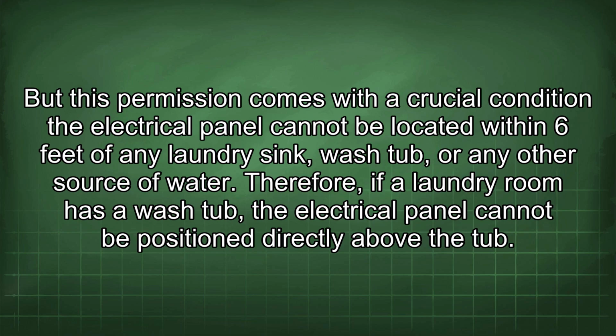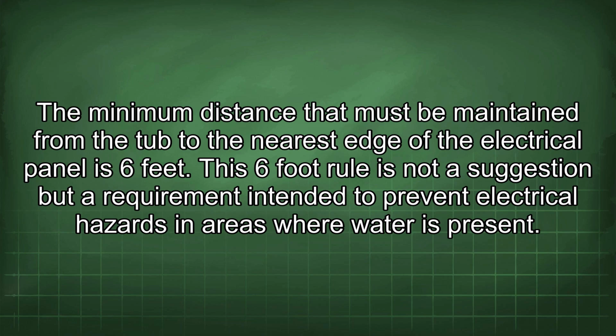Therefore, if a laundry room has a wash tub, the electrical panel cannot be positioned directly above the tub. The minimum distance that must be maintained from the tub to the nearest edge of the electrical panel is 6 feet. This 6-foot rule is not a suggestion but a requirement intended to prevent electrical hazards in areas where water is present.